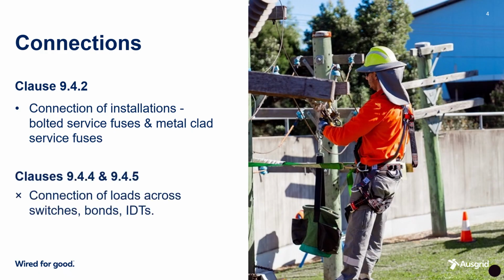New clauses 9.4.4 and 9.4.5 prohibit the connection of electrical loads, for example customer installations or street lighting luminaires, across switches, bonds or inter-distributor Ts. Workers must connect both the active and neutral connections to any load on the same side of the switch, bond or IDT.